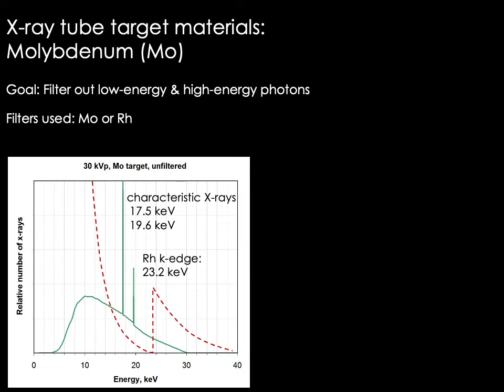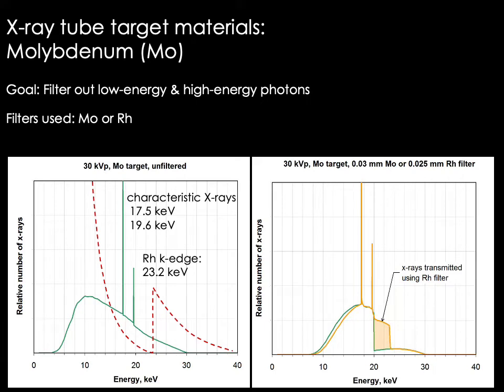Using a rhodium filter on an x-ray beam produced from a molybdenum target: the k edge of rhodium is slightly higher than molybdenum at 23.2 keV, meaning we retain more of the high-energy photons. Clinically, a rhodium filter is used for denser or thicker breasts when these higher-energy photons are needed to adequately penetrate the breast tissue. The molybdenum-filtered spectrum is shown in green and the rhodium-filtered spectrum in orange.